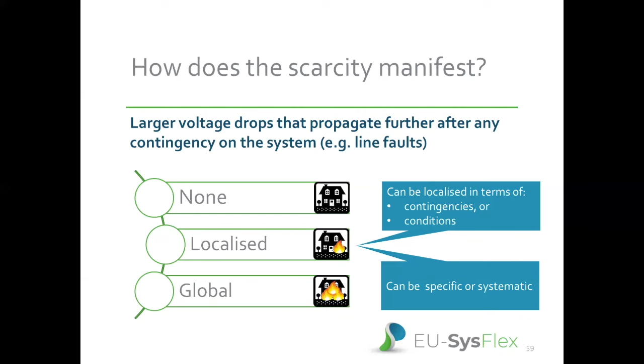So how do we measure that scarcity? We use 2 measures looking at that voltage drop: the number of unique violations, which is how many buses went below 0.5 per unit for a contingency, and secondly the early recovery, which is what percentage of those buses that went below 0.5 were recovered to above 0.5. That's trying to capture the initial drop and then the recovery while the fault is still on. Both measures are during the fault-on period, before it's been cleared.